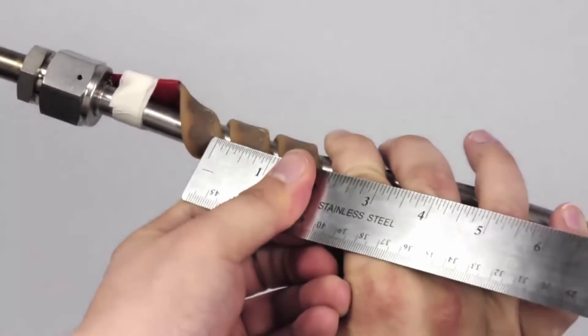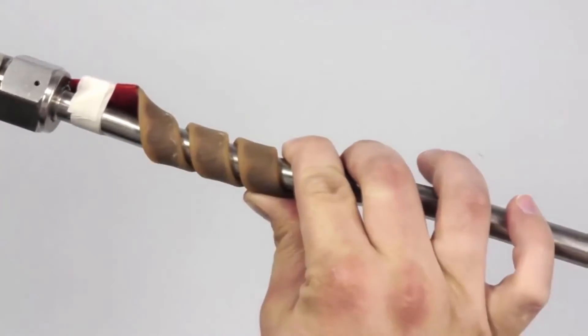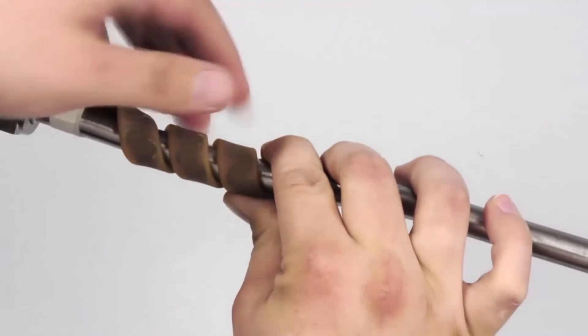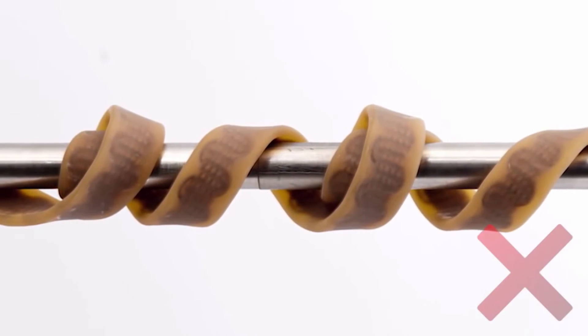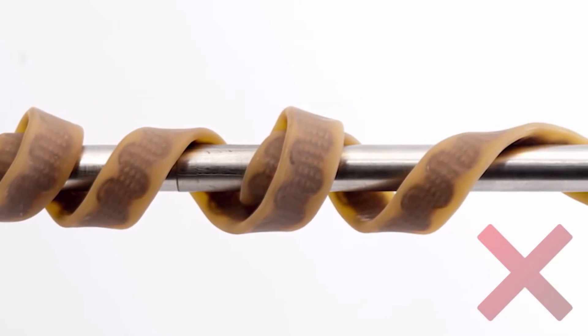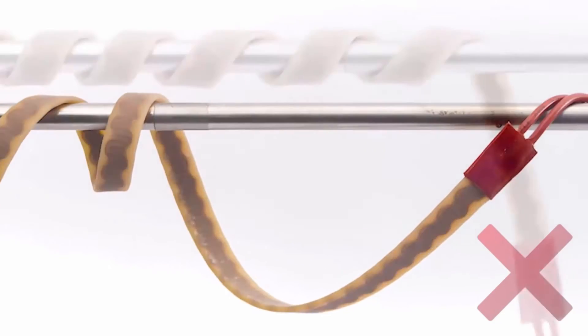A minimum distance of one-eighth inch is required between spiral wraps to avoid damage to the heating tape. Ensure the heating tape is not kinked, twisted, overlapped on itself or hanging free from the surface on which it will be heating.